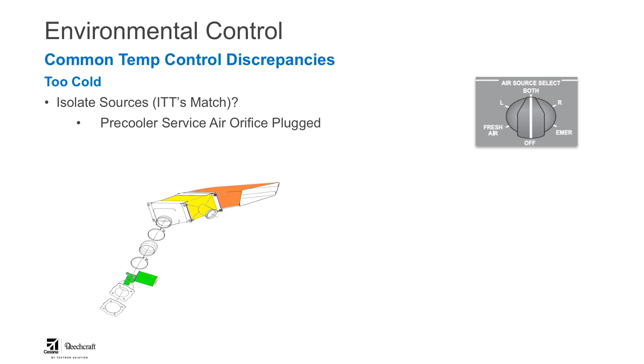In other words, when that probe says, hey, it's time to warm up, I'm going to stop feeding the actuator to open the pre-cooler, it will shut off the service air, but that service air would be trapped if we didn't have an orifice. And if it was trapped, that modulating valve would remain fully open and allow cooling continually. So we put an orifice in there to allow the pressure to bleed off because that valve is spring-loaded to the closed position. So if that orifice gets plugged and that air isn't venting, it could run on the cold side.